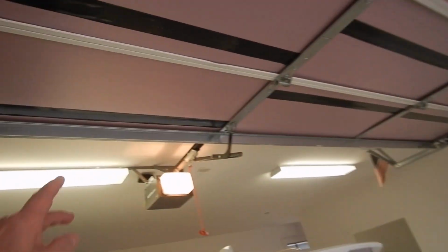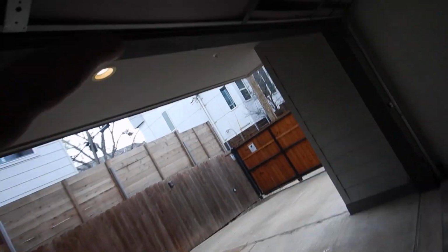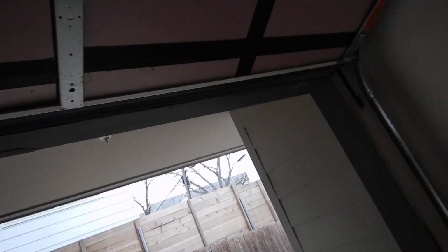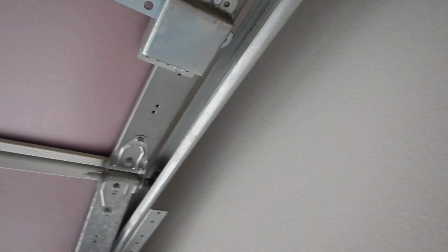So what do we learn? No GFCI. Door's not balanced. The door is noisy. Switch is too close to the floor. We do not have an entrapment notice. Our wires were not connected with insulated staples. We do not have an entrapment notice on the door. We do not have a door pull handle. We learned that the door lock has not been decommissioned.